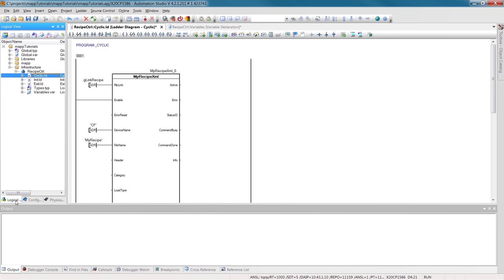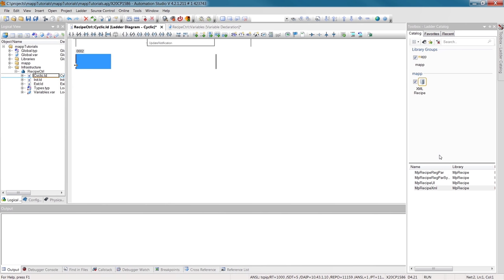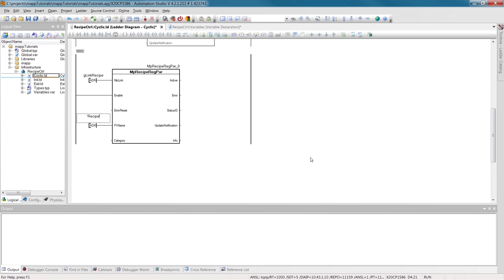Now we're all ready to save and load recipes. Unfortunately, we haven't yet determined the content of our recipe. To do this, we need the component MPRecipeRegPar. For the MpLink, we'll use the same one that we connected to MPRecipeXML. Again, we'll enable the component by setting the enable input. PVName determines the information that our recipe will contain.